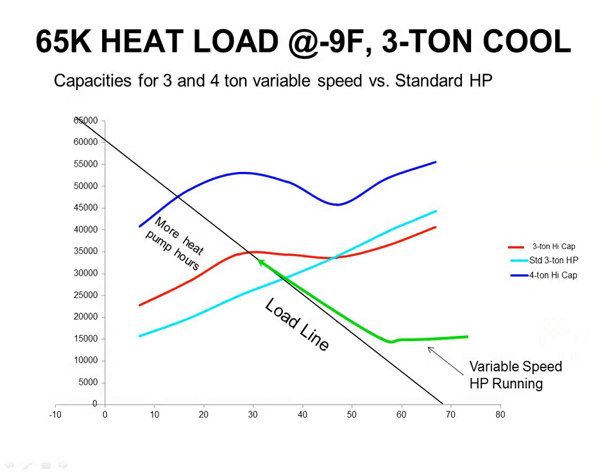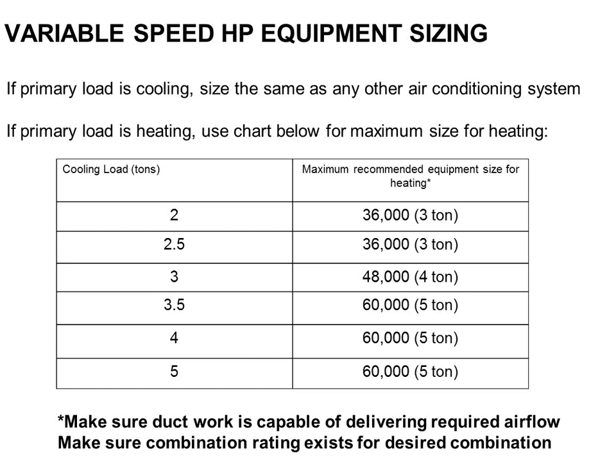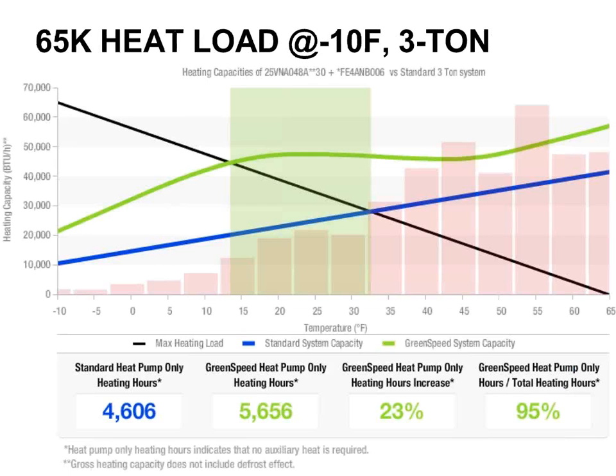That's just a recommended sizing if you want to maximize for heating. You don't have to do that. You can maximize your design for cooling, and that's fine too. You're just not going to get as much heating BTUs out of it. Most variable speed heat pumps do not come in half sizes. It typically goes 2, 3, 4, 5, 6, 8, 10, 12, 16, 18, 20, 24-ton type things. Typically they don't have any half sizes at all. Because of the variable capacity, you don't need to be quite as precise, if you will.